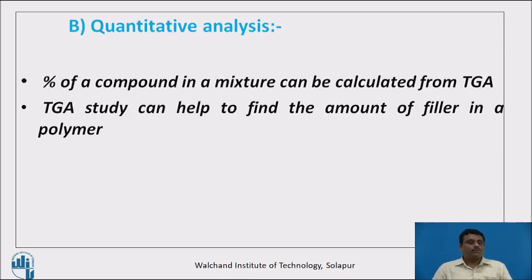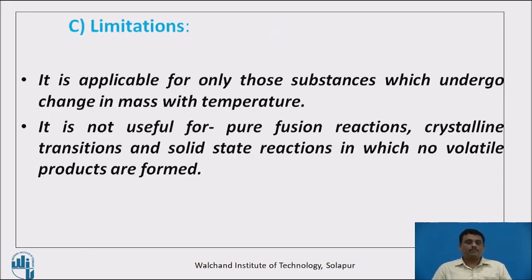For quantitative applications, the percentage of a compound in a mixture can be calculated from TGA, and TGA study can help find the amount of filler in a polymer. Regarding limitations, TGA is applicable only for substances that undergo a change in mass with temperature. It is not useful for pure fusion reactions, crystalline transitions, and solid-state reactions in which no volatile products are formed.